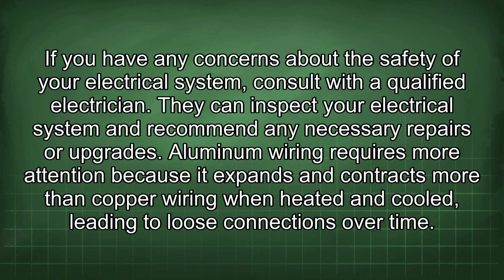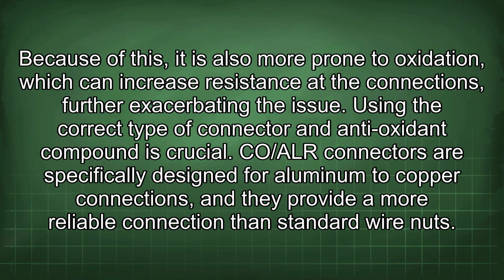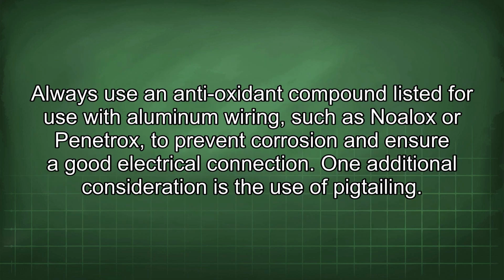Aluminum wiring requires more attention because it expands and contracts more than copper wiring when heated and cooled, leading to loose connections over time. Because of this, it is also more prone to oxidation, which can increase resistance at the connections, further exacerbating the issue. Using the correct type of connector and antioxidant compound is crucial. CO/ALR connectors are specifically designed for aluminum to copper connections, and they provide a more reliable connection than standard wire nuts. Always use an antioxidant compound listed for use with aluminum wiring, such as Noalox or Penetrox, to prevent corrosion and ensure good electrical connection.